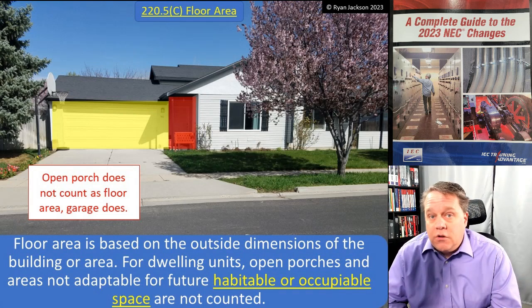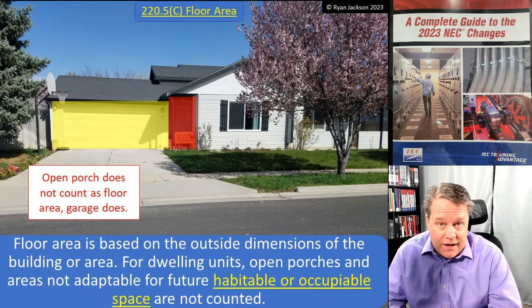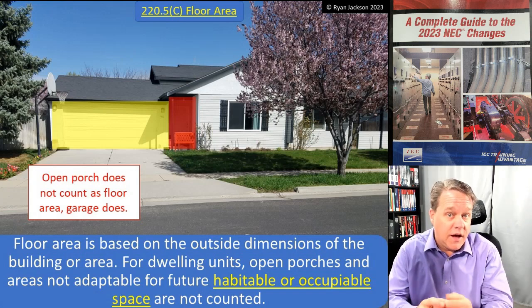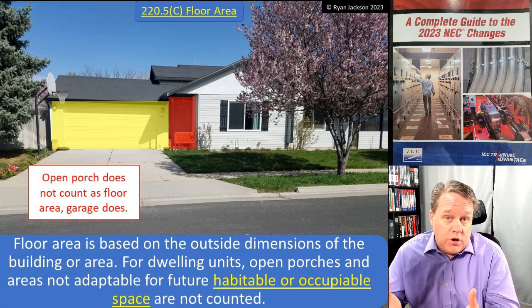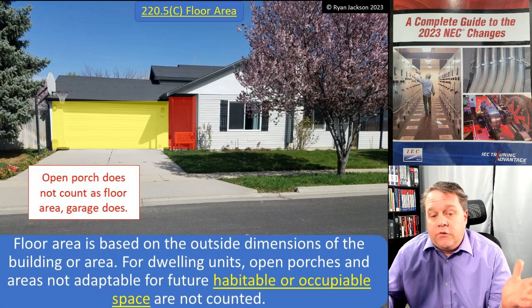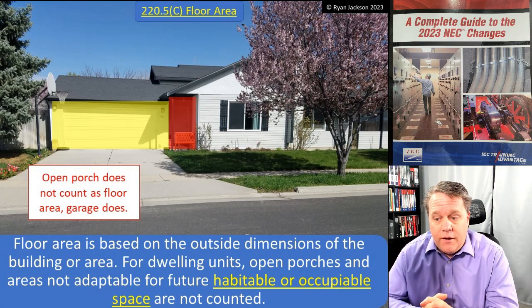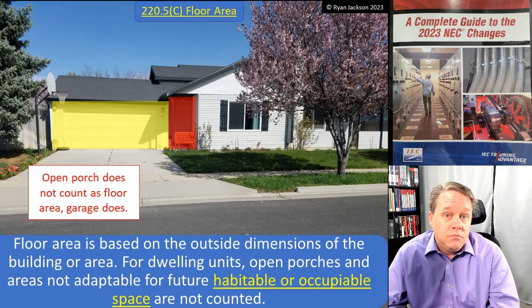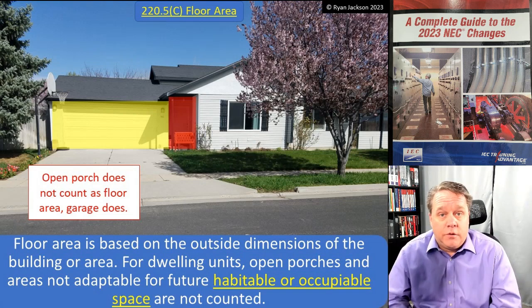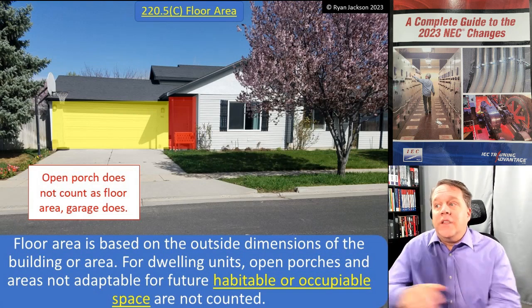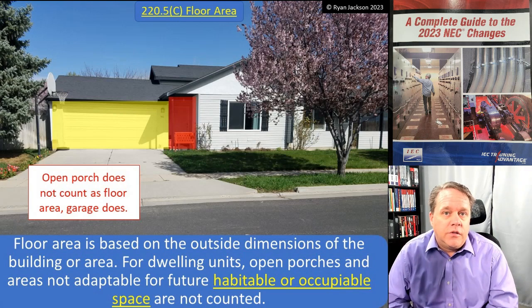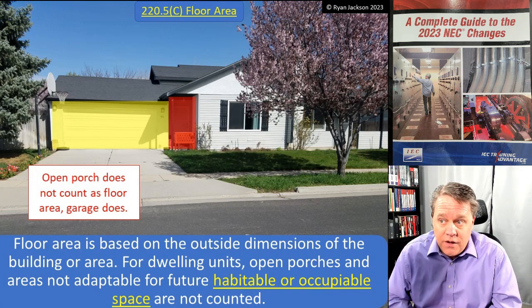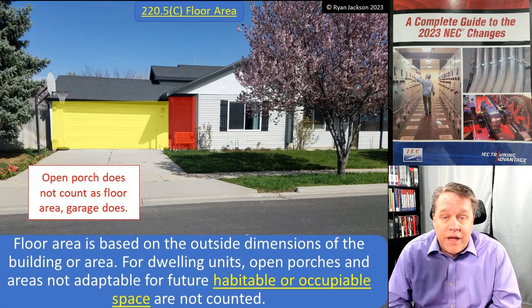To me, that old language did not include the garage, the attic, the crawl space, or a basement without enough ceiling height — but you could argue all of those spaces were adaptable for future use. What's the future use of a crawl space with only two feet of headroom? Storage. What if an inspector said that's adaptable for future storage space and you have to calculate the entire crawl space at 3 VA per square foot? I don't think that was ever the intent, but you could make that argument — you can't make it anymore.